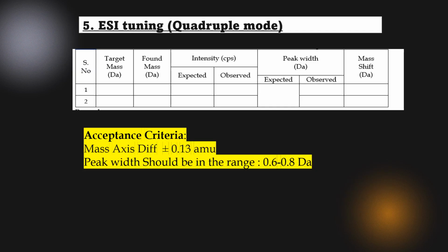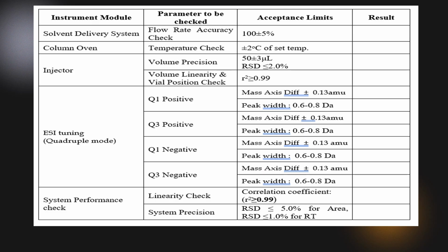Now when you come to MS, that is your detector, the part that needs to be calibrated is your quadrupole. So what you're going to be calibrating here is your peak width and the mass axis difference. And you're also going to check the intensity of the masses. So the acceptance criteria for this is the mass axis difference should be in the range of plus minus 0.13 AMU, and the peak width should be in the range of 0.6 to 0.8 Dalton. Now to summarize this calibration, the parts that are calibrated in HPLC are your solvent delivery system, oven, injector. And when you come to the detector, your quadrupole is calibrated, and there is a system performance check as well.